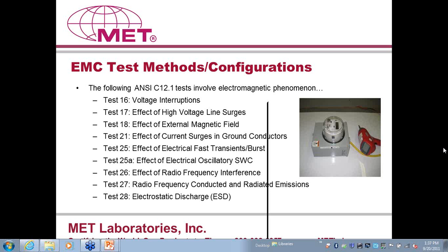Then test number 25A is the effect of electrical oscillatory surge withstand capability, or SWC. This test is intended to verify the immunity of relays and relay systems to repetitive electrical transients. This transient is a damped oscillatory wave which has an amplitude of about 2500 volts, or 2.5 kV, and this is just the amplitude of the first peak. The frequency of this transient is typically 1 megahertz.